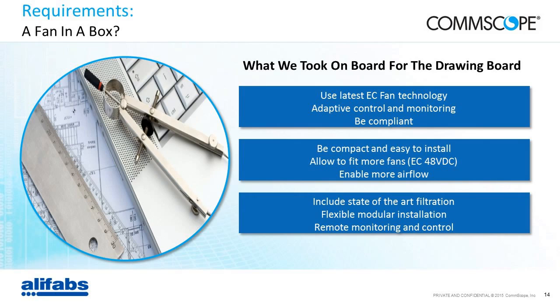The first one is that today's fan technology is fantastic. Electronic commutation allows fans to run from 0% to 100%. Many of them operate on 48 volt DC up to a certain capacity. And we can add adaptive controls, with flexible controls and monitoring. The second key for us was to have a more compact system where we could fit more fans and enable more airflow. And finally, a unique differentiator for our system was to use state-of-the-art filtration, something that not only can sustain for a long time, but also provides great performance and better protection for your critical sites.